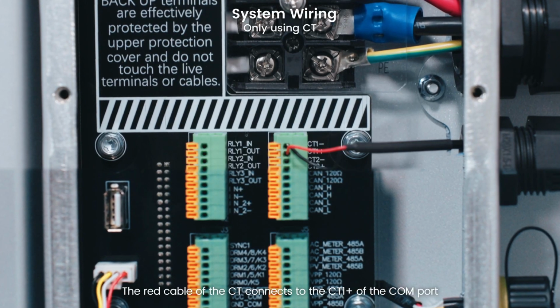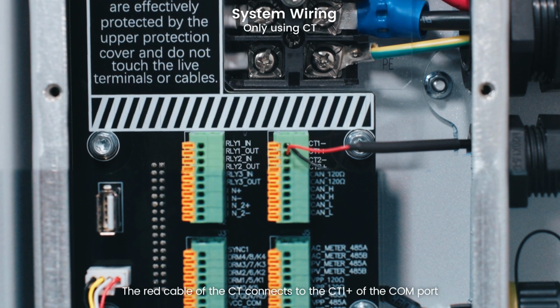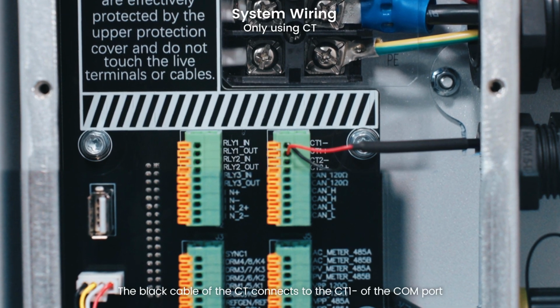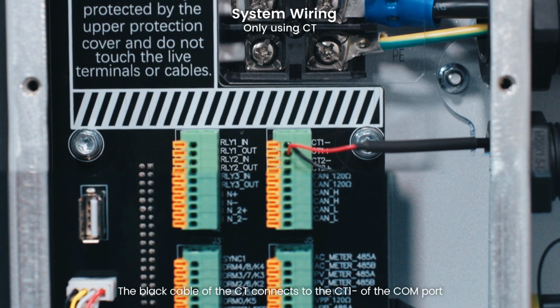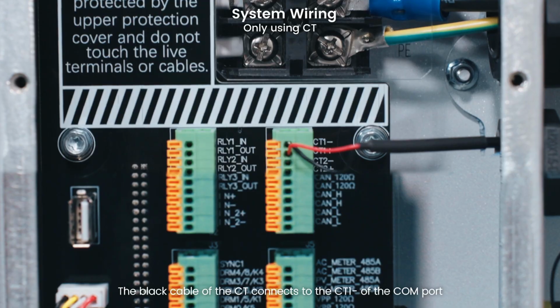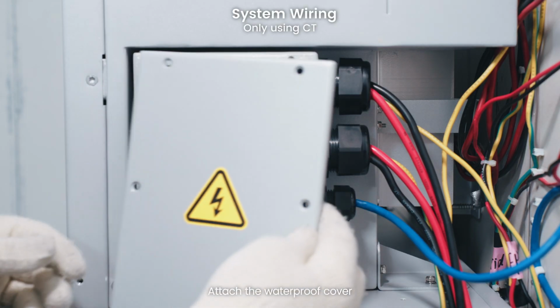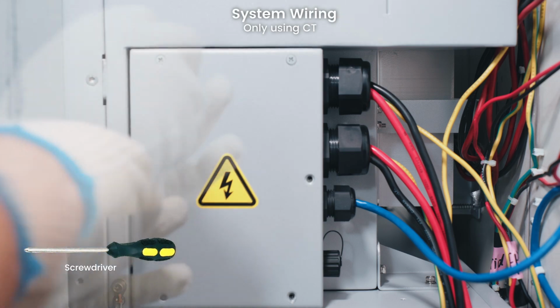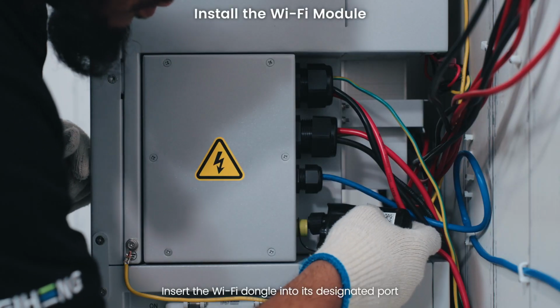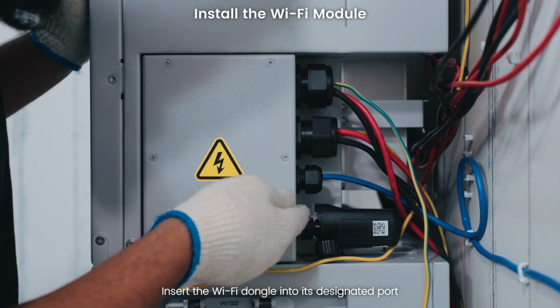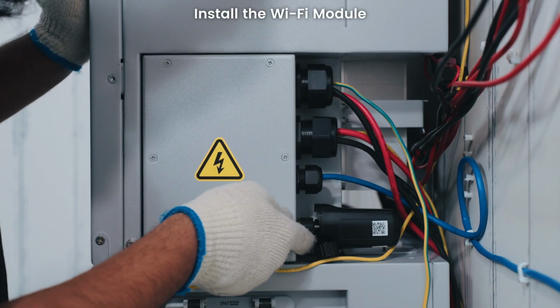The red cable of the CT connects to the CT1 positive of the COM port. The black cable of the CT connects to the CT1 negative of the COM port. Attach the waterproof cover, ensuring it's locked securely in place. Insert the Wi-Fi dongle into its designated port. Tighten the nut.